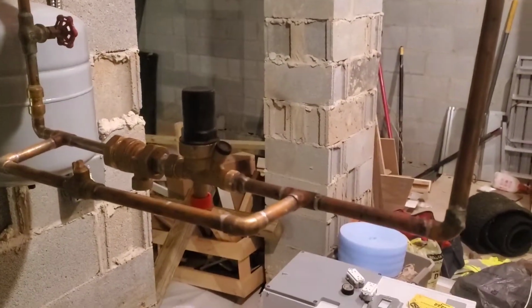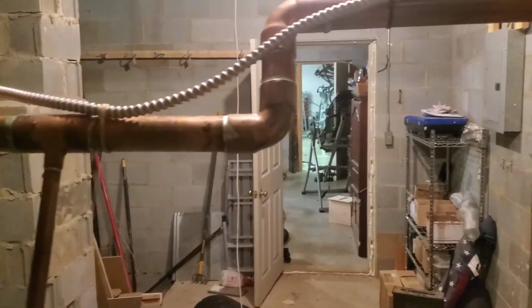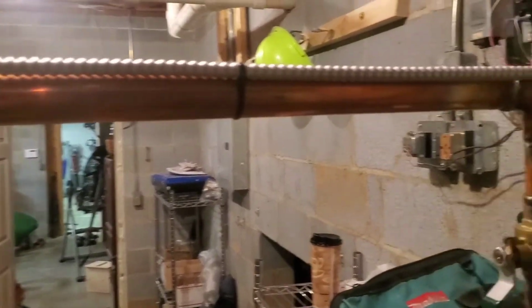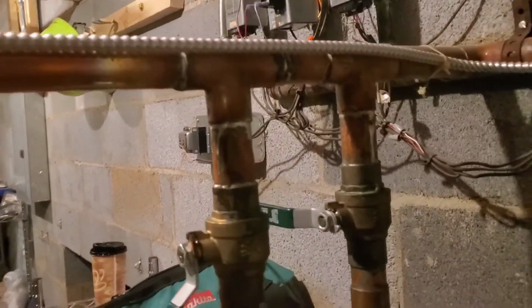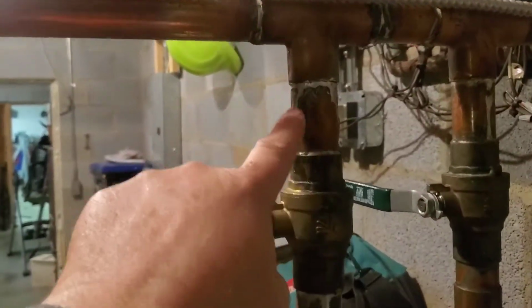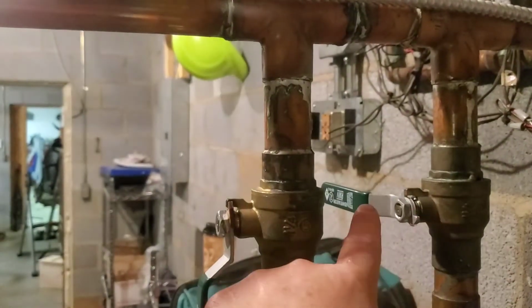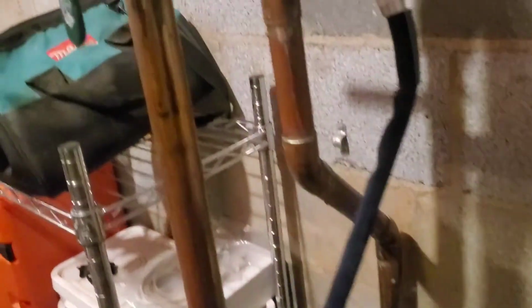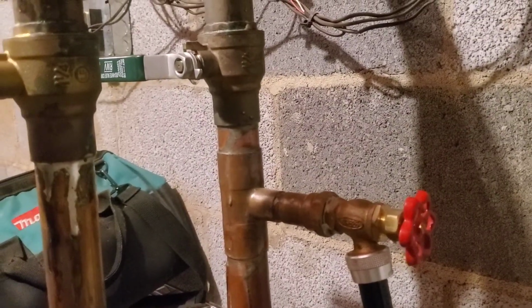So you know what we're doing, of course, is there's the pressure reducing valve sending water in through this 1/2-inch pipe and sending it through the main loop here, and then it has to come down here because it can't go to that valve, so it has to go down through here into the boiler, back out of the boiler, and if there's any air, it has to come out at the boiler drain here. And that's the same way it works with those circuits I was showing you earlier.